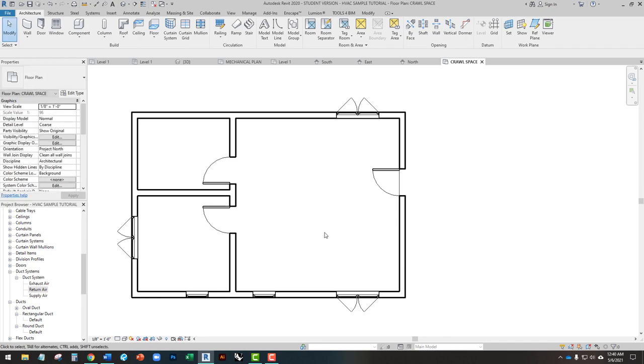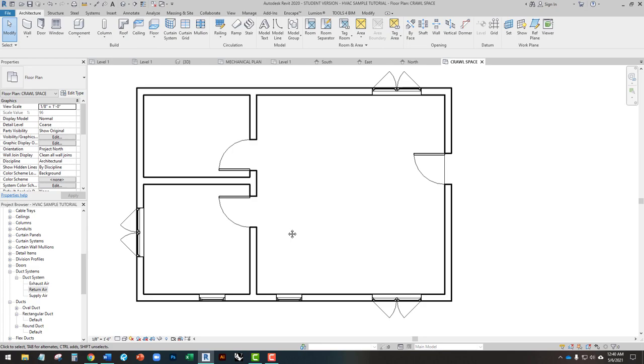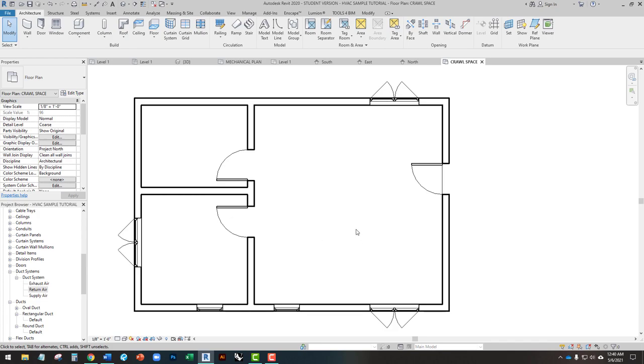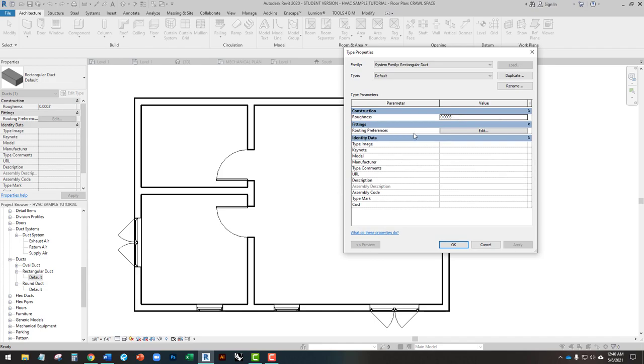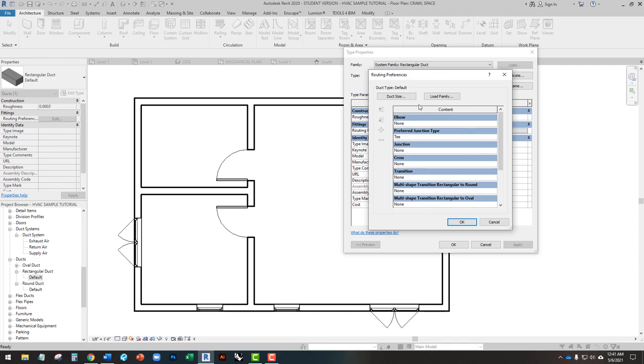We're also going to load a series of connectors — the elbows and T's we need. Normally these would load in the mechanical file if we used the mechanical template, but we're in the architectural template, so we'll have to load some of this manually. We're going to go to Families > Ducts > Rectangular > Defaults and edit the routing preferences, telling Revit how to handle an elbow, a junction, a cross — which family to load in each scenario. So we're going to load all of these.